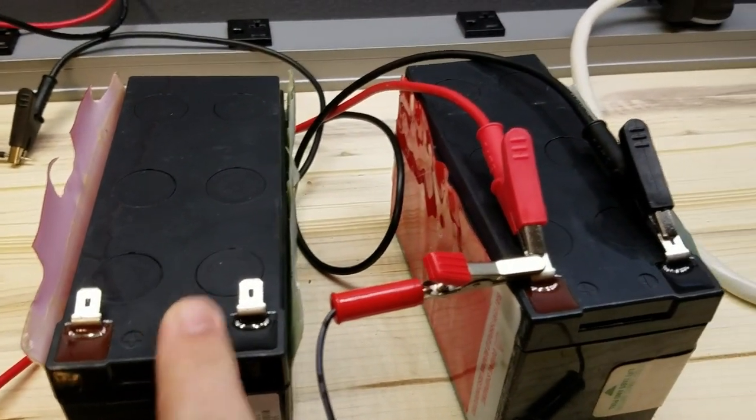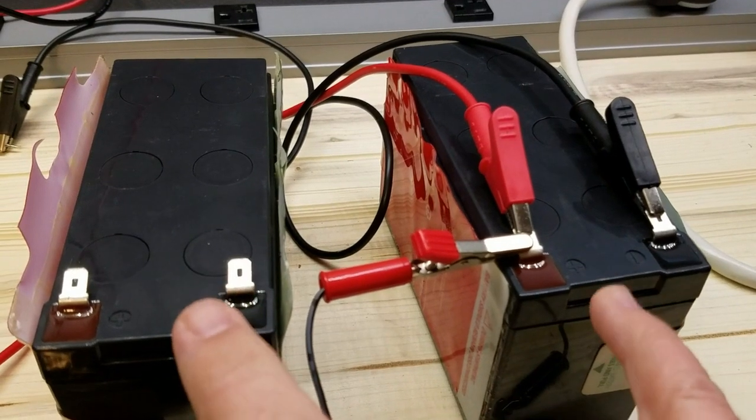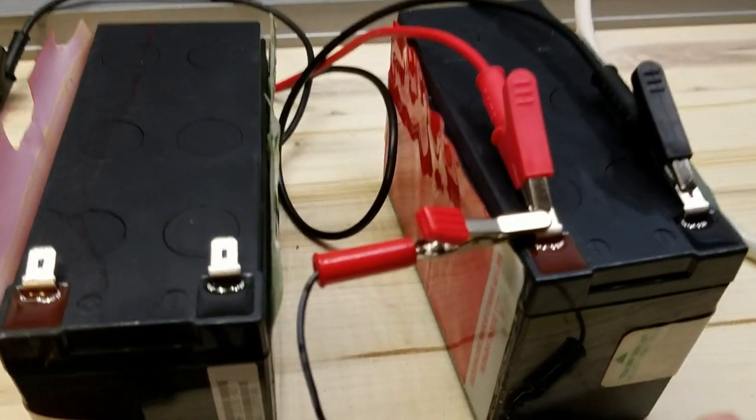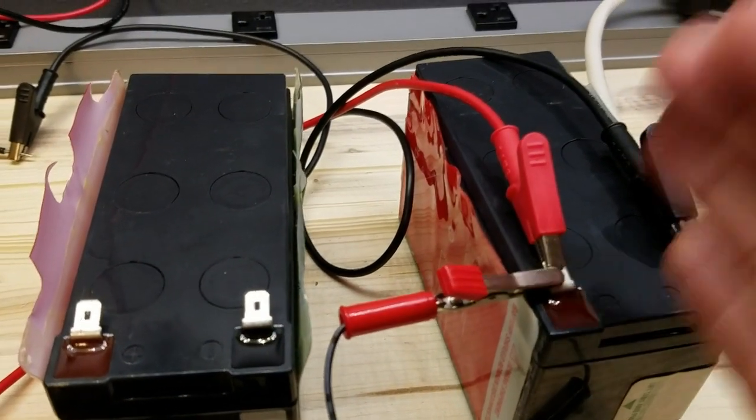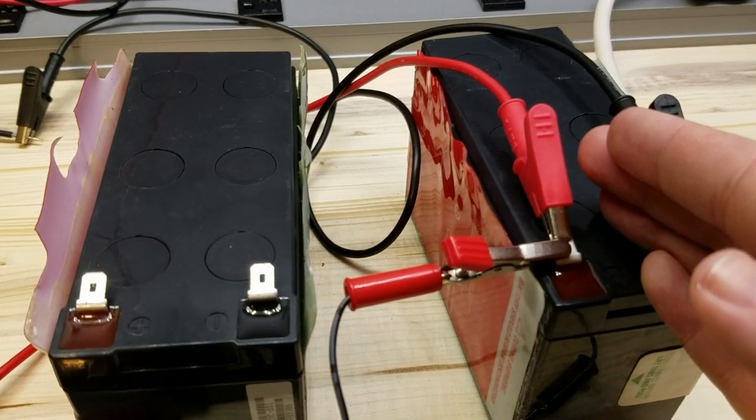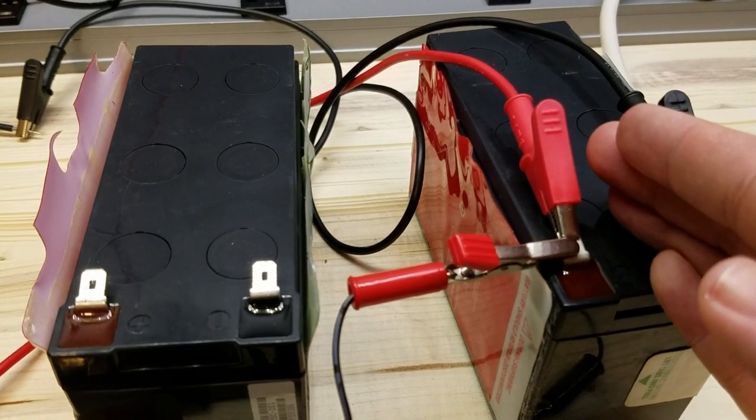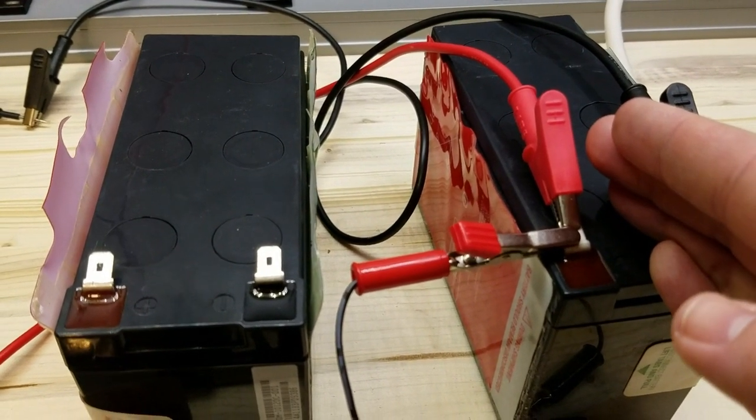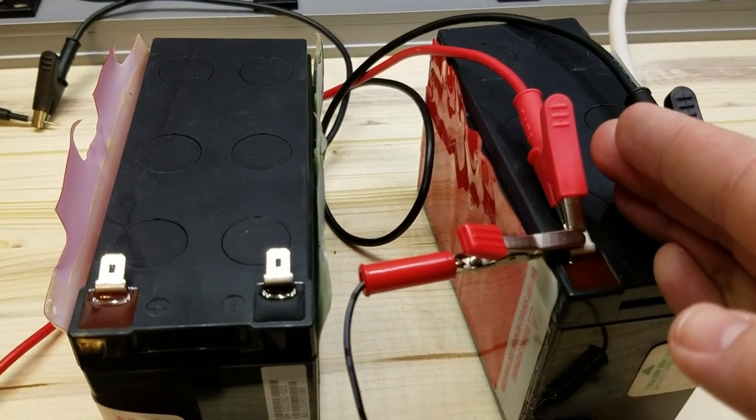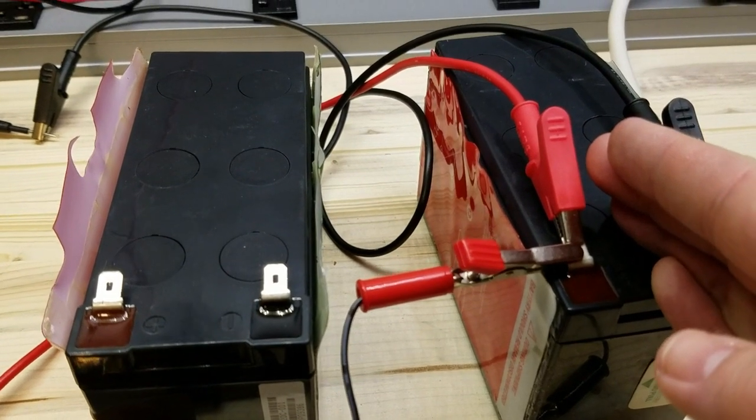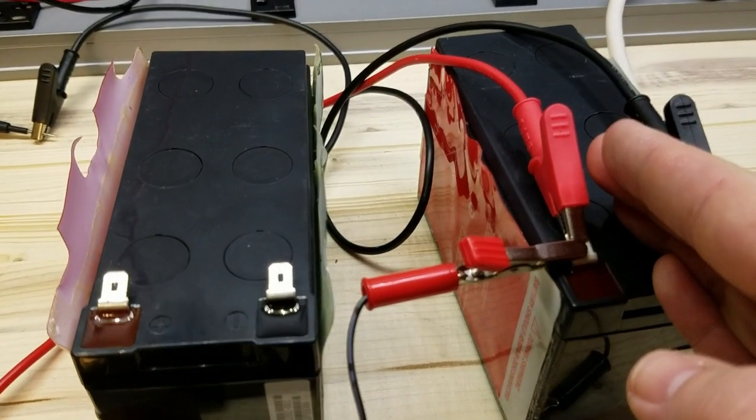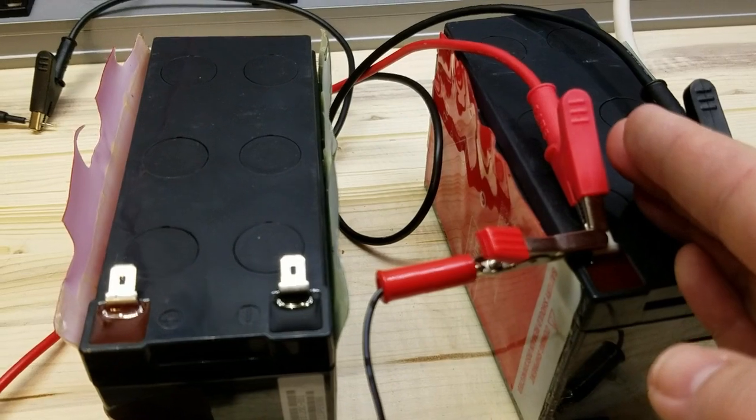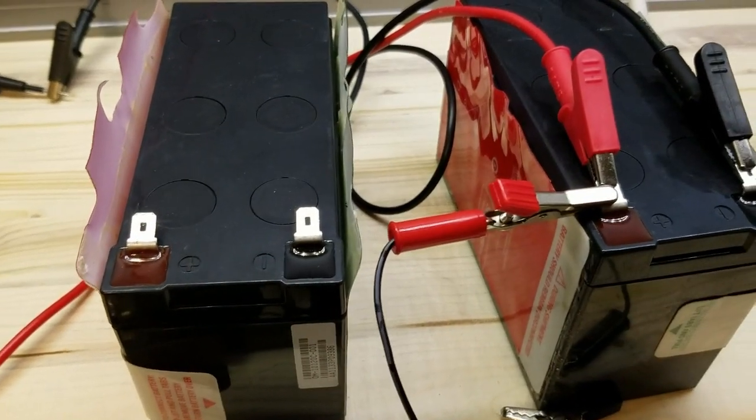Still got some life in her. But these were part of the same pack, so as soon as they started to share a load, this one would cause the voltage to drop so bad that the UPS couldn't take it. So what I'm going to do is I'm going to rip apart the brand new battery pack from APC, and I'm going to see if this is the case.